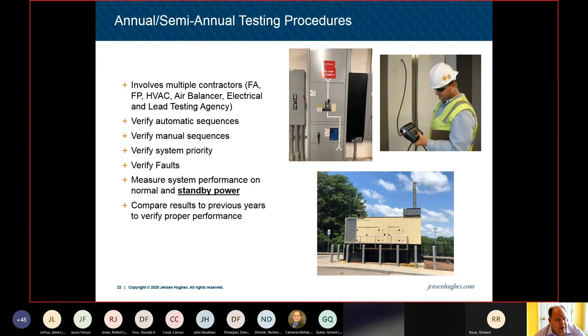The upper right-hand picture is a test, taken from an elevator, where someone is taking measurements from the elevator to the floor for an elevator shaft pressurization system. There's a lot of moving parts and pieces to coordinate with these systems. And then finally, you take all that information: how it sequenced, how it worked, and performance measurements from the air balance contractor. You're able to compare that to results from previous years to verify proper performance.